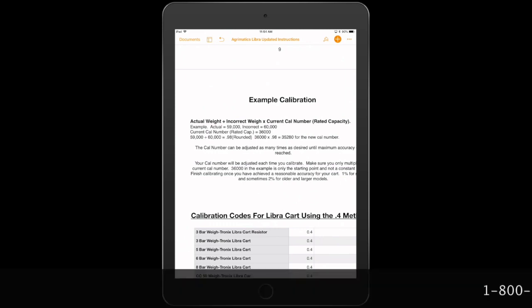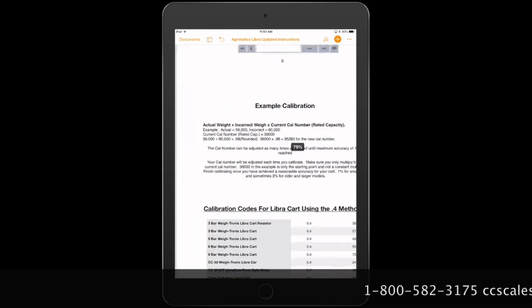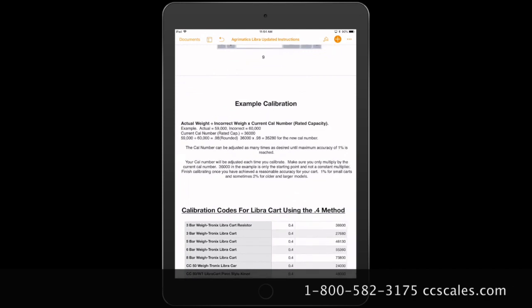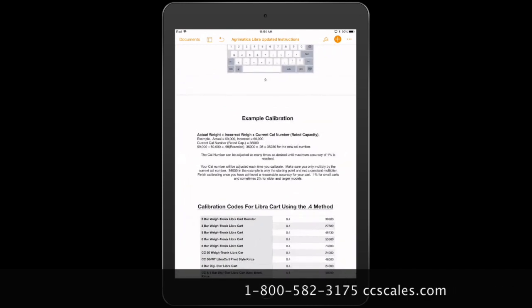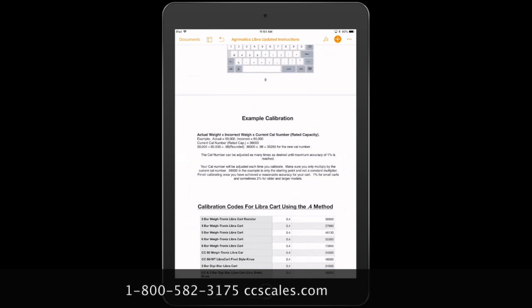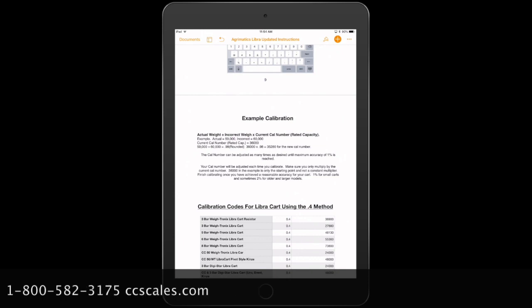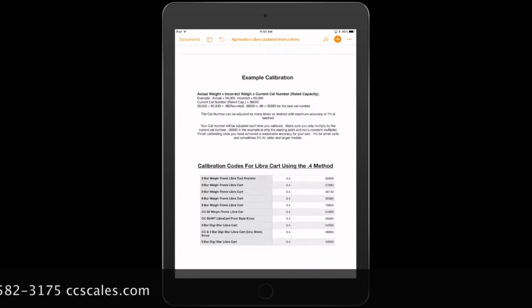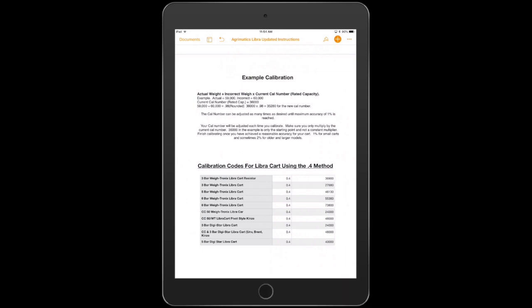That's a little bit different from my example, but it's the same basic formula that applies. In this example, we just used a round number of 36,000. In the one I showed you on the Libra it was 36,900. And once again, the 36,000 or the 36,900 or 40,000 or whatever your number ends up being based on this table, it's just a starting point. So it won't be multiplied by that number each time. It'll change just a little bit based on the percentage of error and how you change it.